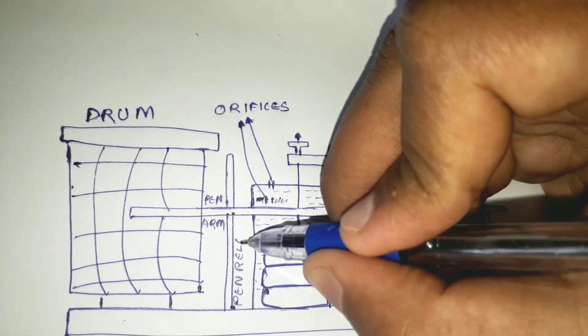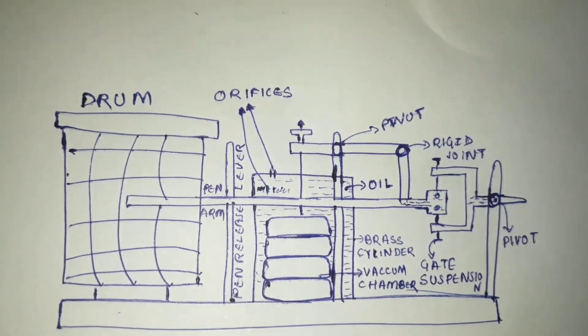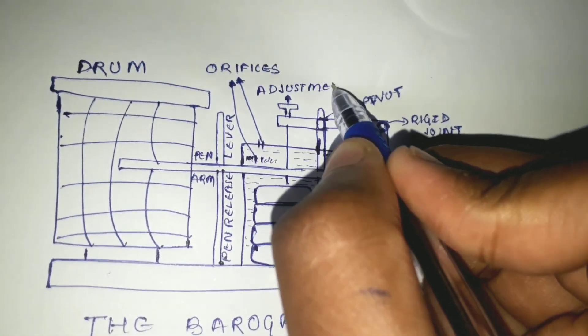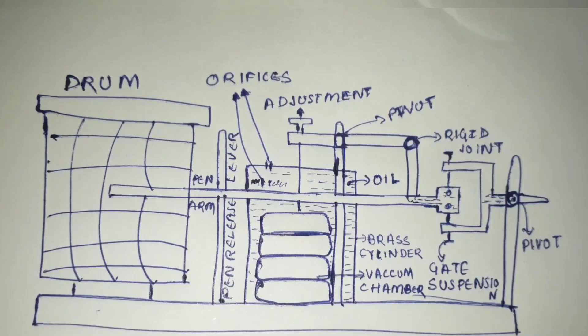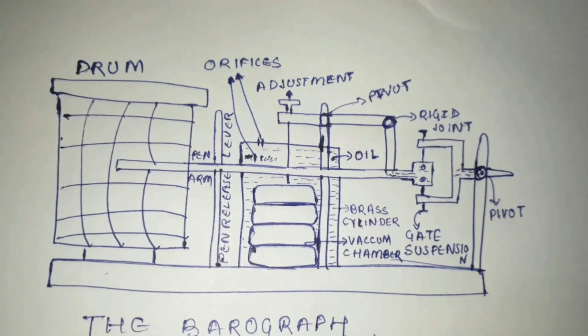As you can see in this picture, the vacuum chamber is immersed in a brass cylinder of oil. So what is the purpose of that oil? When the chamber expands, the oil is forced out of the top of the cylinder through small holes, and when the chamber contracts, the oil is sucked into the cylinder.